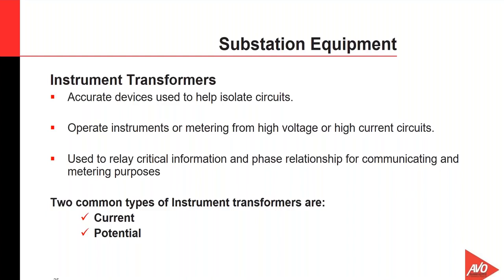Current transformers are the current sensing units of the power system, meaning that in my mind, these current transformers are going to be the eyes of our substation, and they're going to see any type of problematic situations, and they're going to be able to recognize it, and they're going to be able to control that breaker to open that circuit under a fault condition.